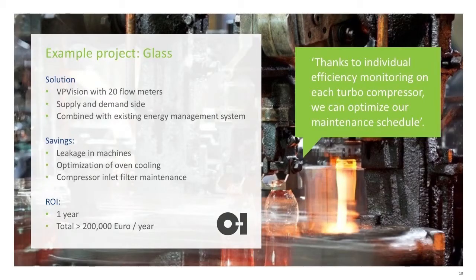Another example of what you can realize with energy monitoring is this glass factory. We do a lot of glass factories, and most glass factories have large compressed air systems. Typically, the installed compressors will probably cost you like 1.5 to 2 million a year. And those factories are often quite old, so there's a lot of savings opportunity there. And this is just an example where, similar to the steel factory I showed before, the compressed air was used for cooling. So they changed compressed air cooling to blower-based cooling for the oven.